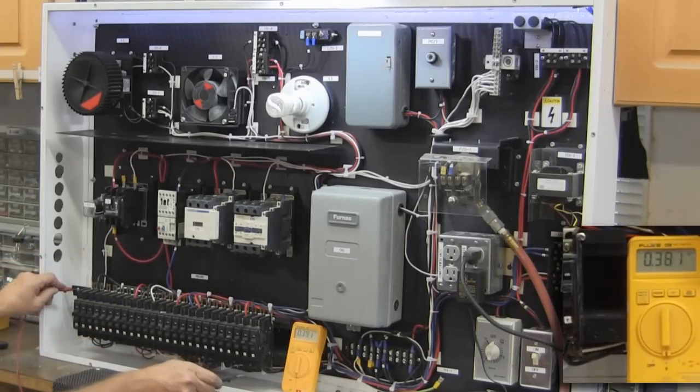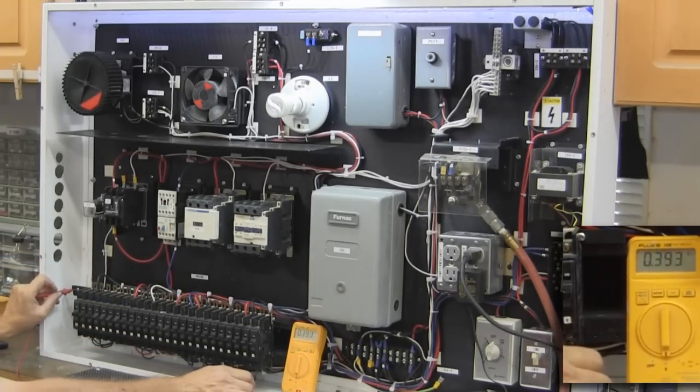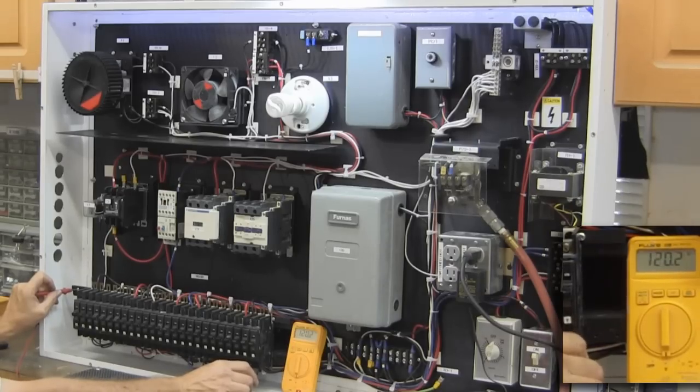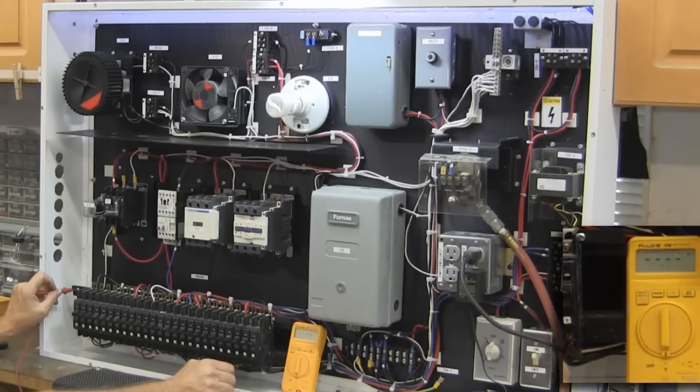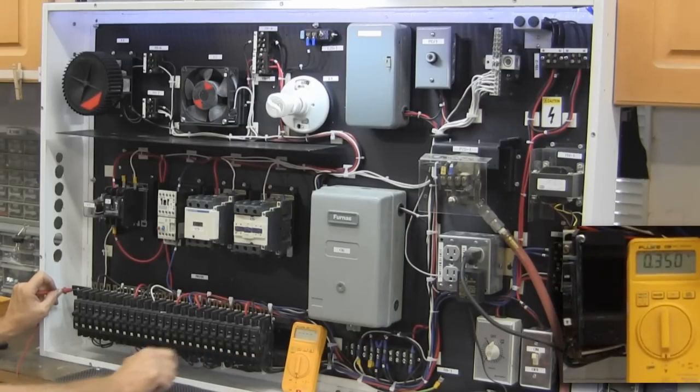Now I'll go down below here to the line side of these and I'll check. There I've got 120 on the Y, 120 on the X, nothing on W. And then just on down the line you just run through and you can test your voltages.